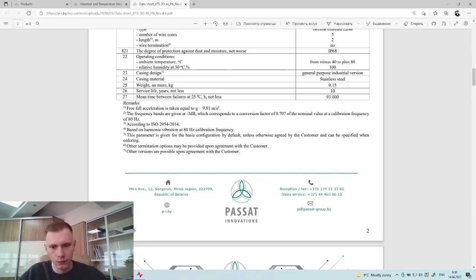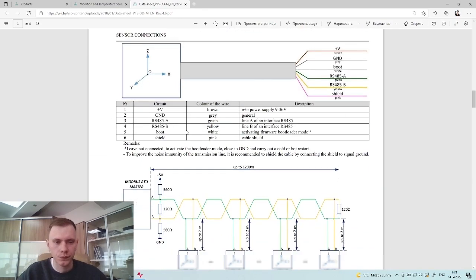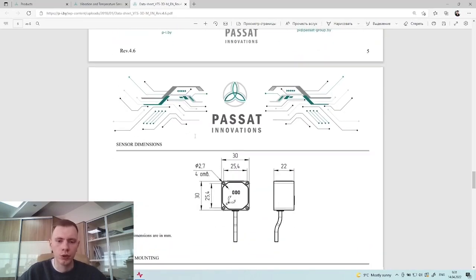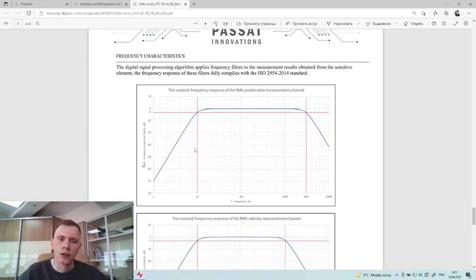Frequency bands are given at -3 decibels, which corresponds to a conversion factor of 0.707 of the nominal value at a calibration frequency of 80 Hz. So we have to put in some filters described in the standard ISO 2954, because it is required if you want your product to be a verified measurement unit. You need to comply with these frequency filters. And here we have a graphical description of this filter.